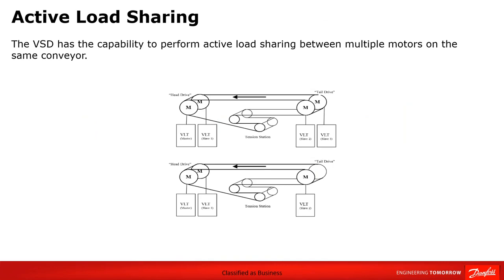So if we take a look at this slide, the variable speed drive has the capability to perform active load sharing between multiple motors on the same conveyor. So you can see here we've got the head and the tail end. One variable speed drive assumes the function of the master and the other functions as a follower. The master variable speed drive sends its actual speed to the follower, which the follower then uses as its speed reference. Not only does it send that, it also sends its actual torque to the follower, which the follower uses as its torque producing current limit setting. So in this way, as the master's torque increases, the follower's torque limit increases as well.